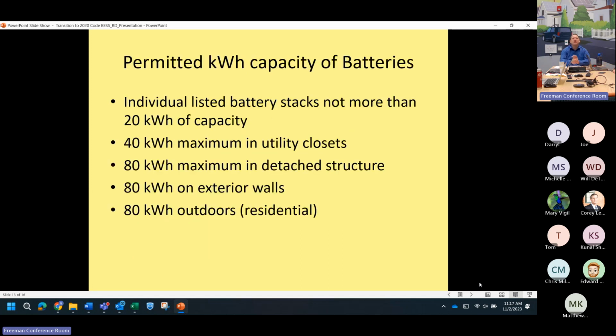Next, permitted capacity of batteries. This is something you generally don't have to worry too much about because your manufacturer has already thought about this. For example, Generac has an 18 kilowatt hour stack, and a lot of them are 10s — they're already pre-designed to take care of this problem. But there are maximums. For example, if you have a Generac and want to put 60 kilowatt hours of storage in your utility closet, that goes above your maximum, so you're only going to be allowed to do 40. Each battery stack maxes out at 20 kilowatt hours of capacity, and that's generally already taken care of by the manufacturer.